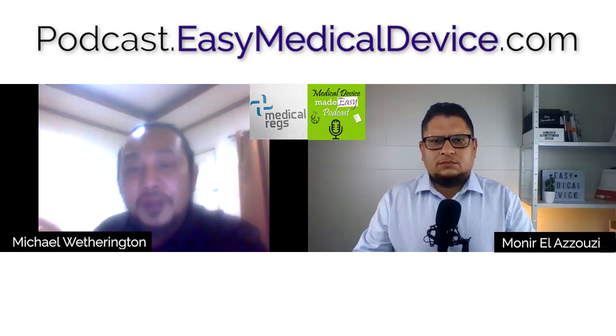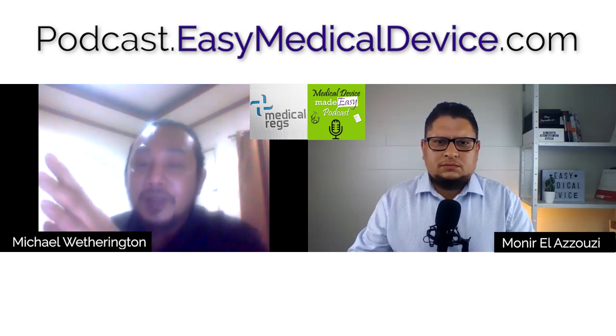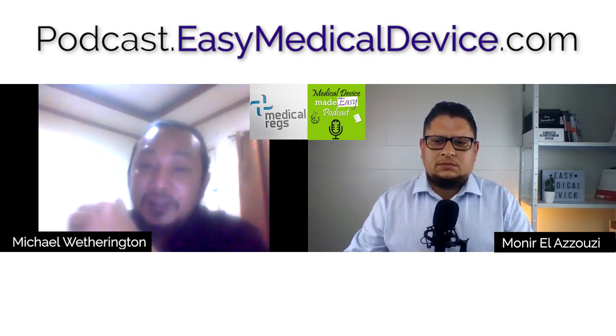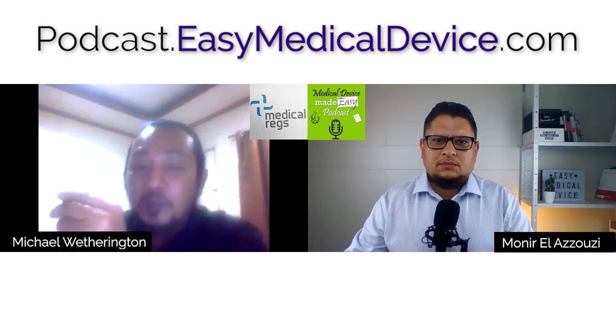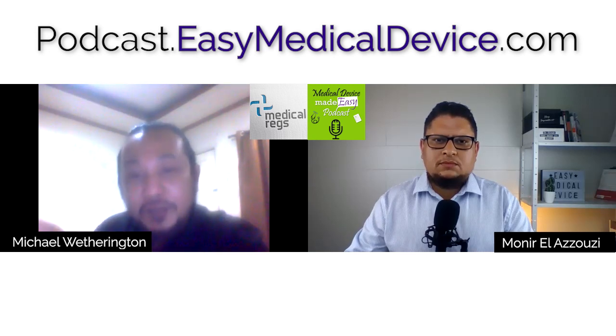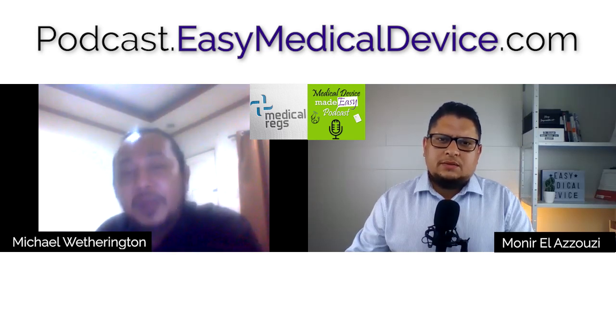And take note that not all manufacturers will have the complete set of test equipment to perform all of the tests. But some of the basics, like leakage currents and high-pot tests, will give you an idea whether you're going to pass the test with high margin or not. So it is always a good idea, even if you have to rent some of the test equipment as a one-time use throughout your development, because it will give you higher confidence before you submit. It's not about submitting blindfolded and just praying that you will pass. There are better ways: check it yourself, performing as much as you can of what the test lab will do to your device as part of their certification. That's a key thing I try to point out to a lot of manufacturers, MedTech startups especially.